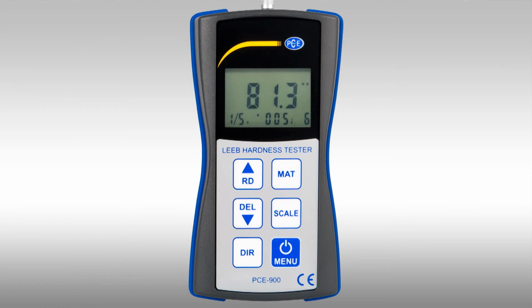It is practical to test the surface on more than one spot to get a middle value. Bottom left of the display you can see 1 of 5 measurements have been done. That means to get a middle value, 4 further measurements can be done. So let's just do that. The middle value for this moulding piece is actually 84.1 Brinell.